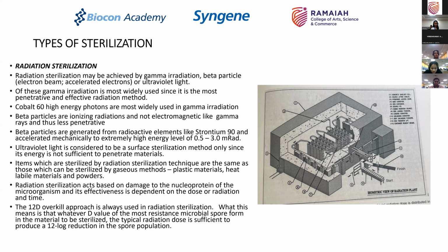When we look at single-use bags, which are manufactured in a factory, and before they are supplied they have to be sterilized, then gamma irradiation is the way of doing it. You can't dry heat them, you can't moist heat them, because both of them will destroy the plastic material. So gamma irradiation is a methodology which is used. You could use ETO, but gamma is much safer, and therefore gamma is used.